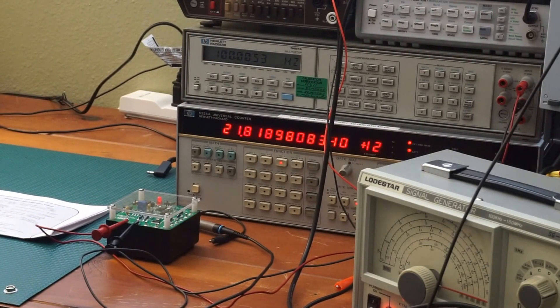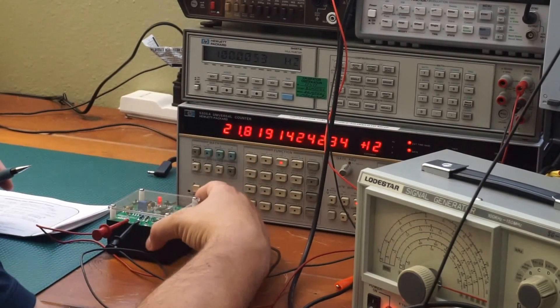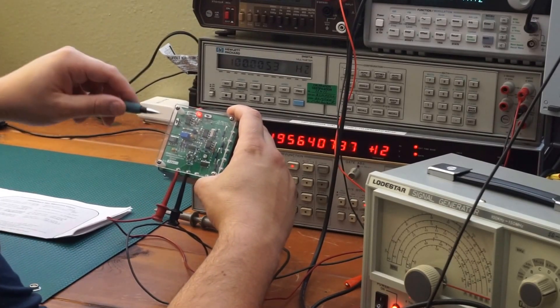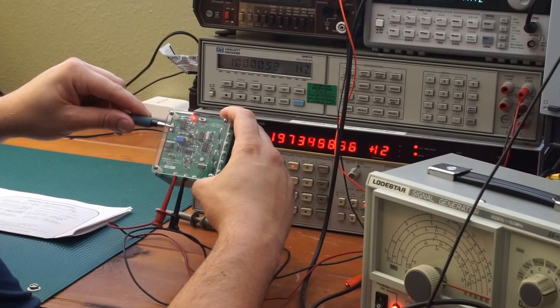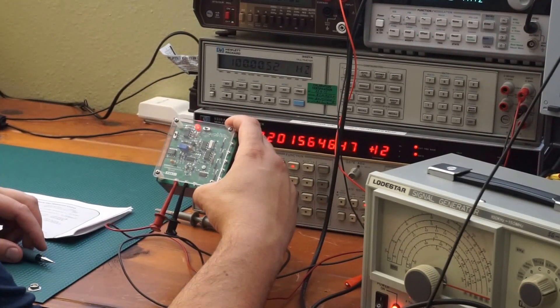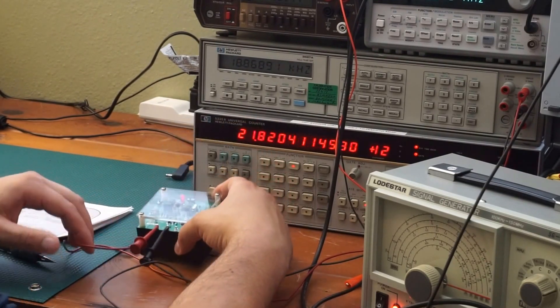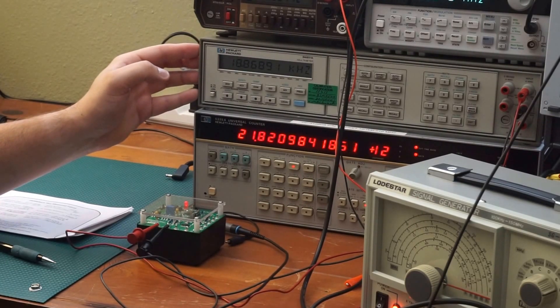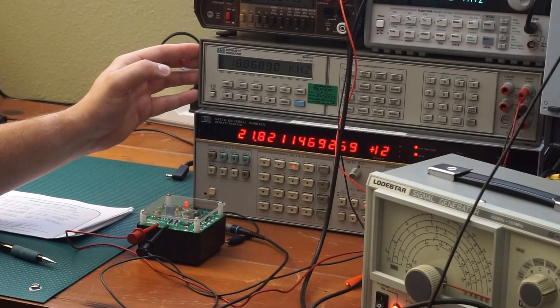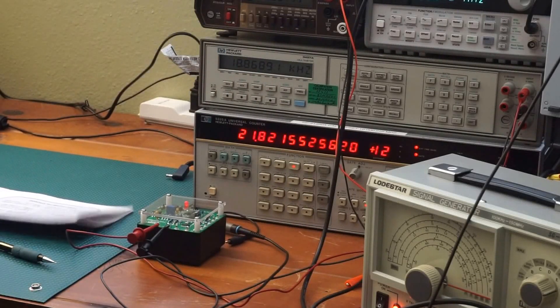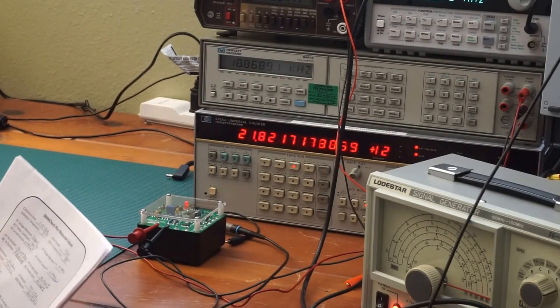So the way you change frequency ranges on this is just to reiterate you can only verify frequency if you're in the AC range. So you move it back to the DC and back to DC and now it should be in the 19 kilohertz range. I apologize about my HP 3457A not refreshing very quickly. I have my number of power line cycles set to 10 just so it removes some of the gross jitter.